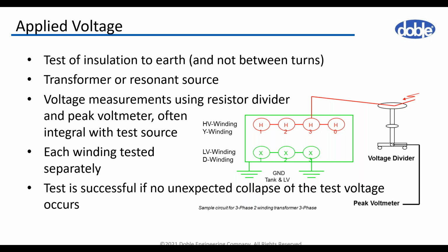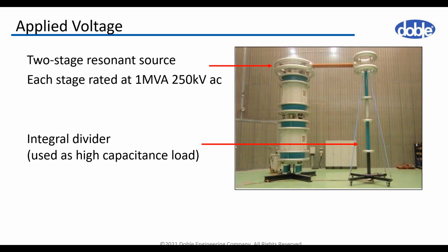Duration of the test is 60 seconds, and the test frequency should be higher than 80% of the rated frequency. The test is successful if there is no collapse of the test voltage. This is how a dedicated resonant test system looks like. The source consists of two stages, 250 kV each, and a voltage divider. The peak voltmeter is not present in that picture because it is located in the test room.